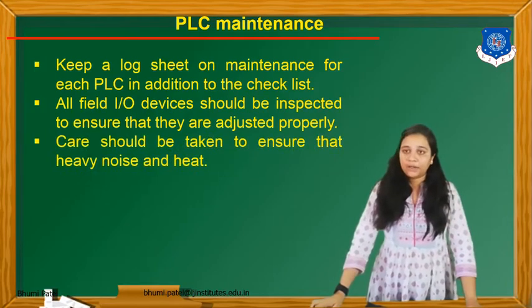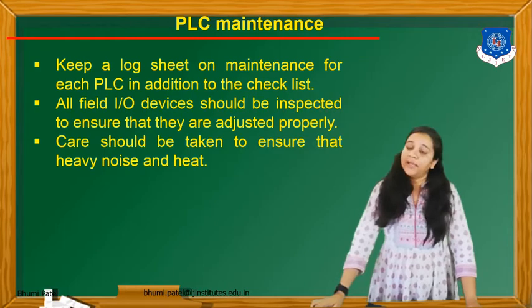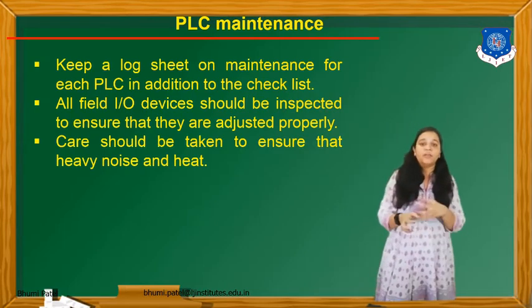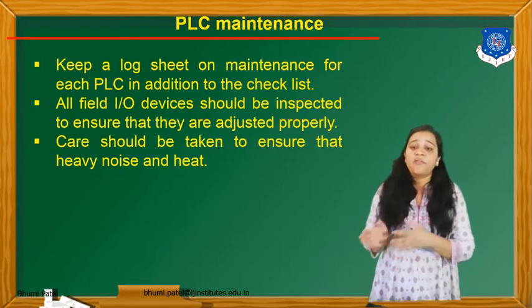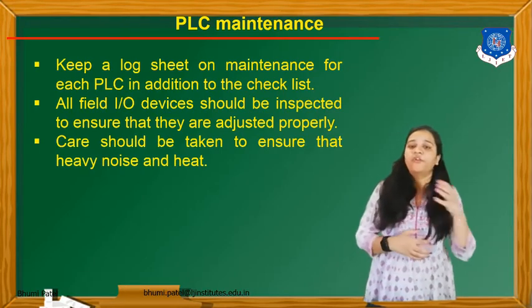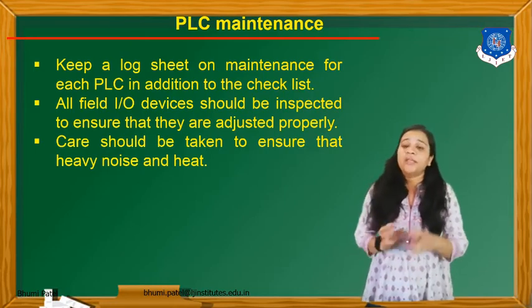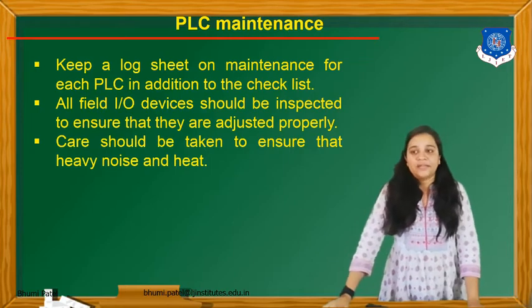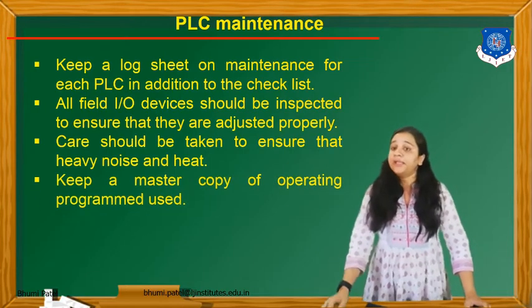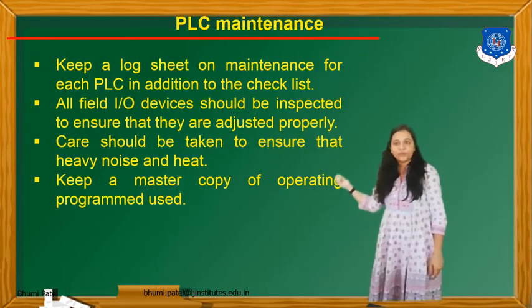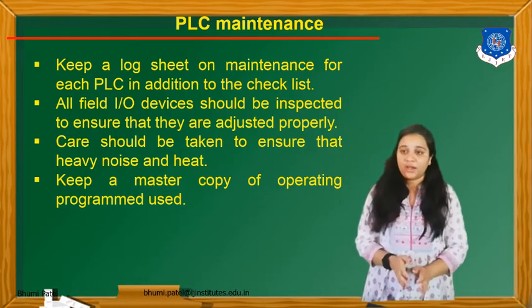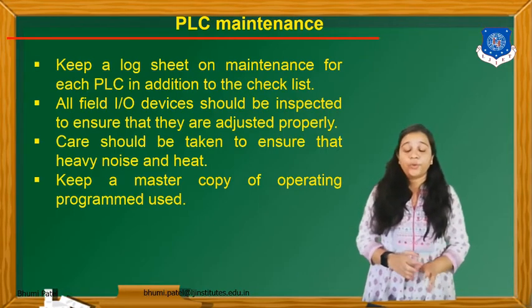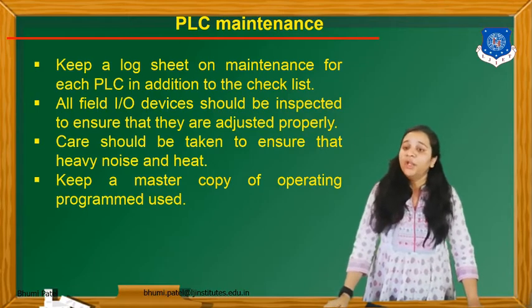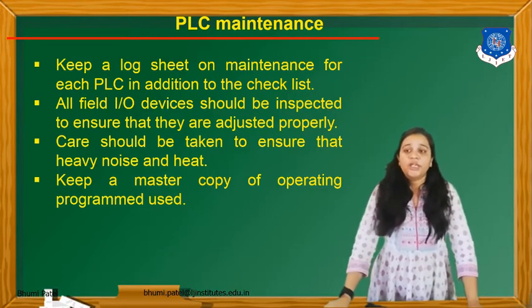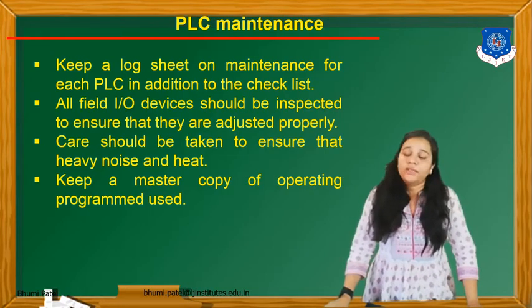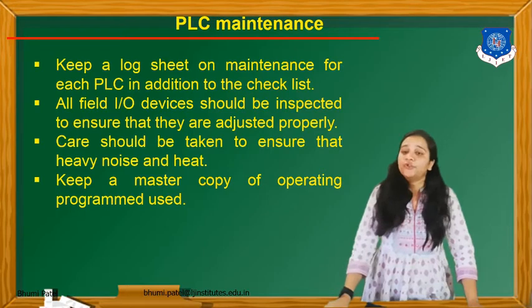Now care should be taken regarding heavy noise and heat, because if heavy noise or heat is generated in this system, it is one type of input entering this closed loop system, and that will affect the output. So we have to take care of heavy noise and heat, and keep a master copy of the operating program used. Whenever the programming is done and we get the proper and perfect output, we have to keep a master copy of that operating program. In future, if there is a problem with the software or the hardware connection, we can easily use this master copy.